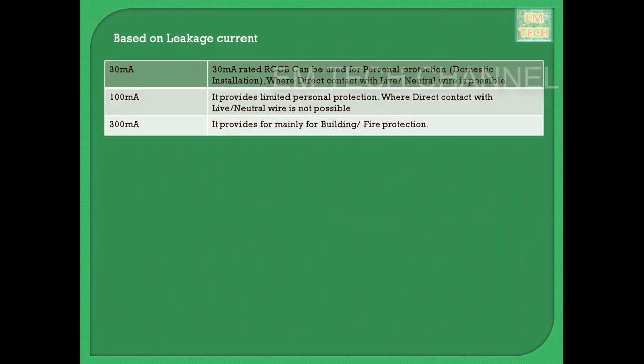Now, this is the major factor, and often when purchasing an RCCB, only this factor is considered and the other 3 factors are left out by most people. This factor is based on leakage current. The 30 milliamps rated RCCB trips a circuit when leakage current is more than 30 milliamps. It can be used in places where personal protection is required and where direct contact with live and neutral wire is possible. A 100 milliamps rated RCCB provides only limited personal protection, and is used where there is very little chance of direct contact with live and neutral wire.